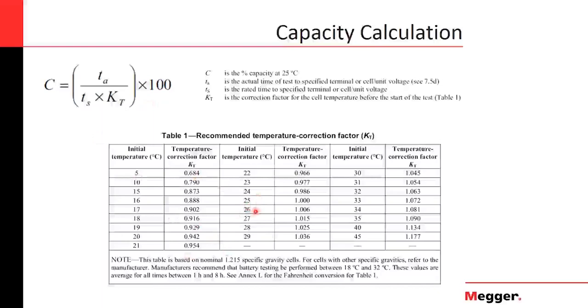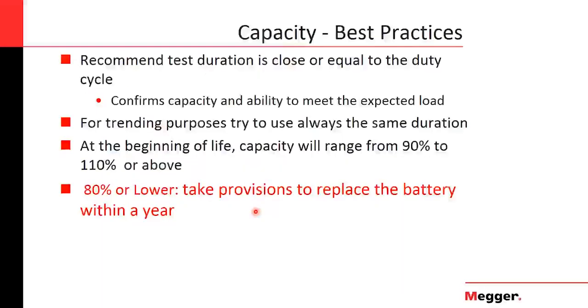You saw in that table there were options for different times, and this is one of the main things with capacity testing, that it might be a long test or a resource-demanding test. To be able to reach those 200 amps or 150 amps, you might need bigger equipment or more load, so you might not have the resources, and you have to spend more time running the test. And that's why it's a test that is not performed that often. In addition, it affects the life of the battery a little bit.